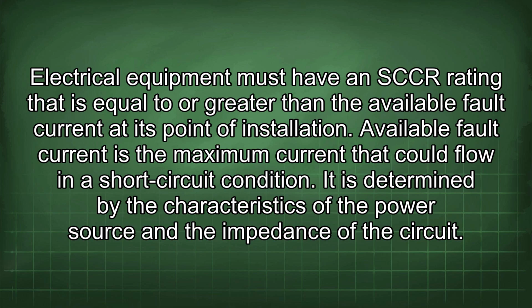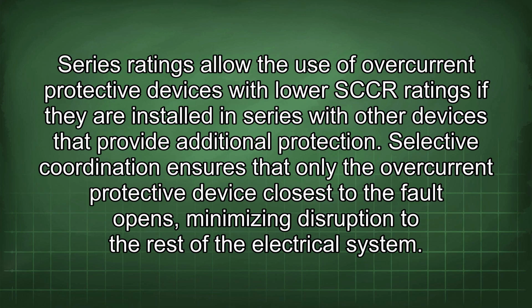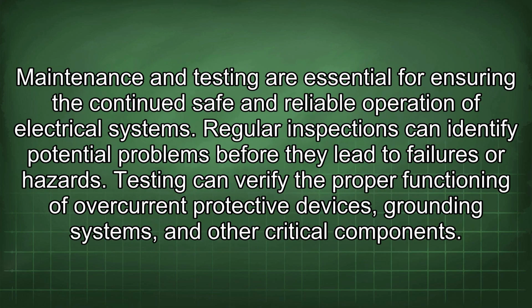point of installation. Available fault current is the maximum current that could flow in a short circuit condition. It is determined by the characteristics of the power source and the impedance of the circuit. Series ratings allow the use of overcurrent protective devices with lower SCCR ratings if they are installed in series with other devices that provide additional protection. Selective coordination ensures that only the overcurrent protective device closest to the fault opens, minimizing disruption to the rest of the electrical system. Maintenance and testing are essential for ensuring the continued safe and reliable operation of electrical systems.